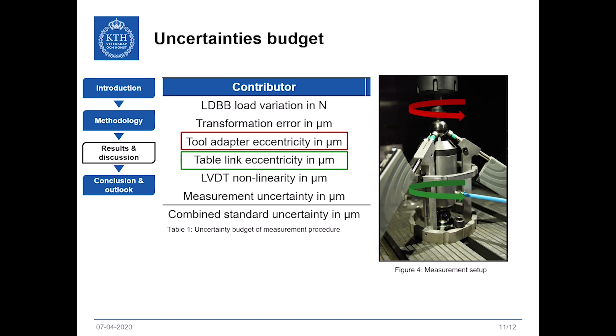It quantifies the difference in measured deflections for the same position of the tool adapter and the table link due to indexed angular loaded double ball bar positions at different load levels. The loaded double ball bar has been rotated in 5 repeated measurements about its own axis of rotation at indexed angular positions of 0, 120, and 240 degrees. The combined standard uncertainty is displayed in Table 1.